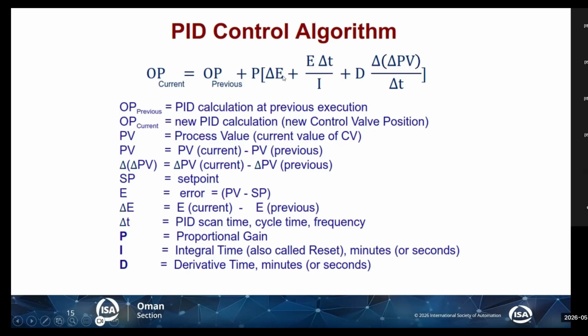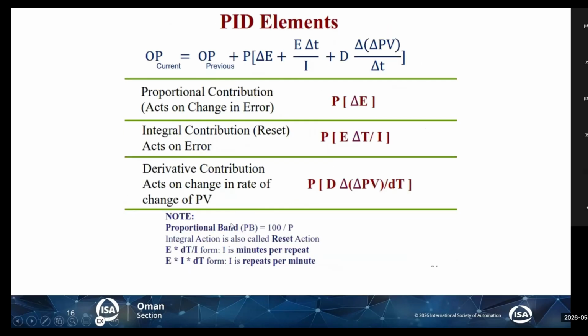This is our proportional effect. This is our proportional gain. And then plus error times the difference in time divided by the integral time, this is our integral, plus the derivative. Derivative is the rate of change of the process value. So if PV is not changing, D will not change. You can see here that the proportional contribution acts on the change in error.